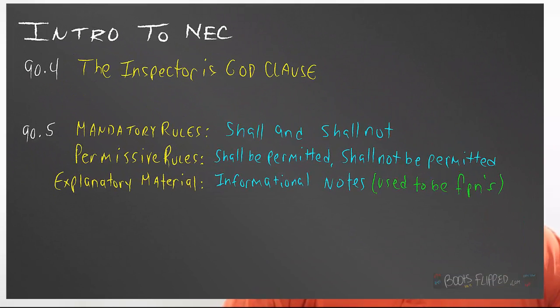We move on to Article 90.5 — that is rules that we have to do. Those rules say shall and shall not — mandatory rules. You have to do it or you can't do it. The next set of rules you're going to see in the code are permissive rules, which are shall be, shall not be — maybe or maybe not. Then we have informational notes, which is basically what all the annexes are. We'll find informational notes all throughout the code — they're notes to give us best practices. They used to be called FPNs or fine print notes; they are now called informational notes.